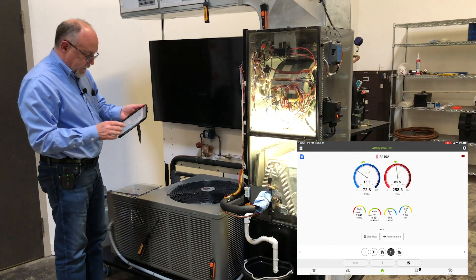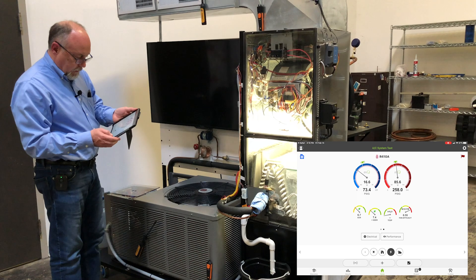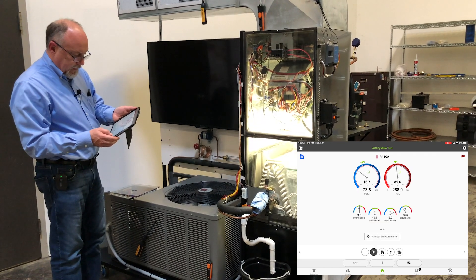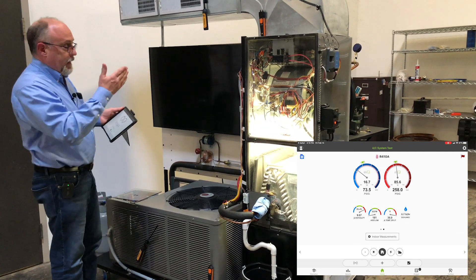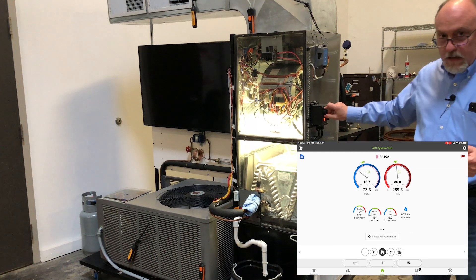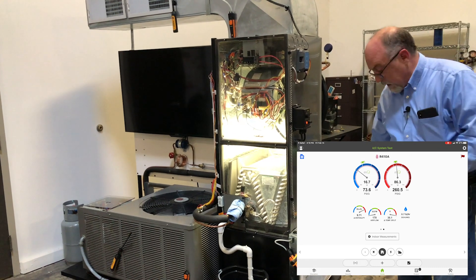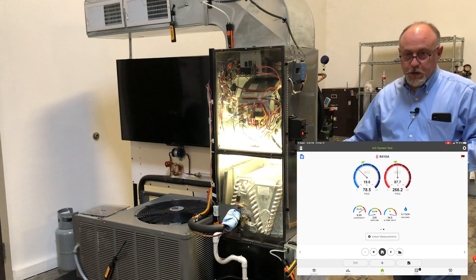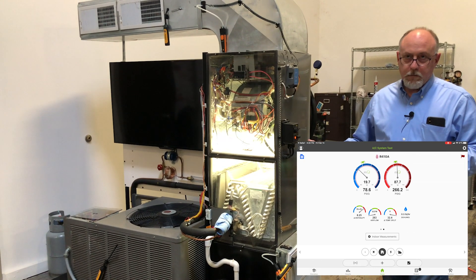Now when I go into my toolbox and turn on my FieldPiece probes, I'm going to get actual temperatures and pressures from both the FieldPiece tools and the Sensi at the same time, so I can see everything going on. I definitely have a low airflow situation — I know that because I have a rheostat cranked down. I'm going to turn that back up. This could be a dirty filter, a plugged evaporator coil, or even — I saw one online where a customer left the plastic on the filter — anything like that could cause this type of low airflow problem.